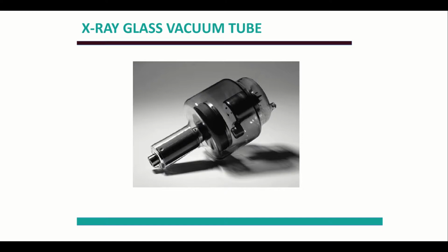So there's a glass vacuum tube encased with a lead housing on the outside of your X-ray head so that the radiation only comes out the opening or portal where there is no lead, and that is where the radiation is going to come out and be aimed at your patient.